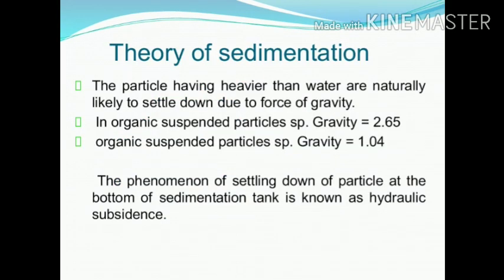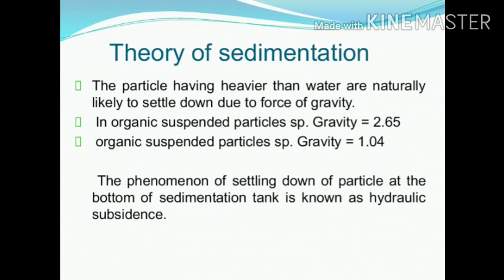Theory of sedimentation: particles present in water, which may be heavier or lighter, may settle down naturally under the action of gravity. For inorganic suspended particles the specific gravity is 2.65, and for organic suspended particles the specific gravity is 1.04. The phenomenon of particles settling to the bottom of the tank is known as hydraulic subsidence.